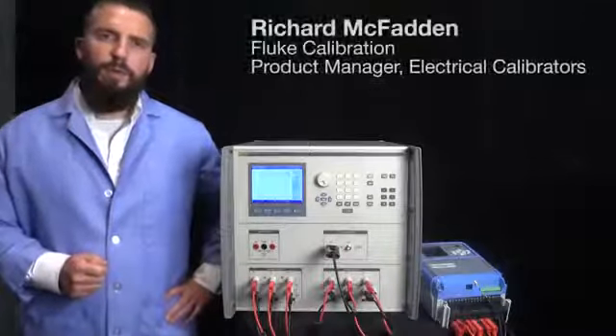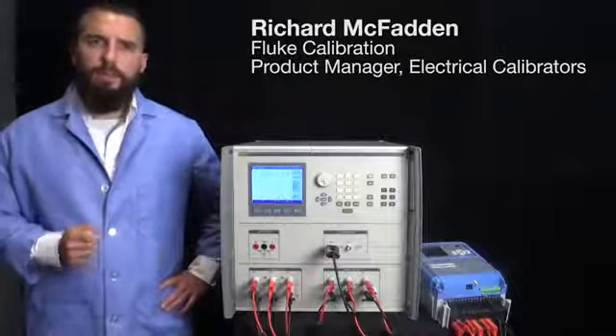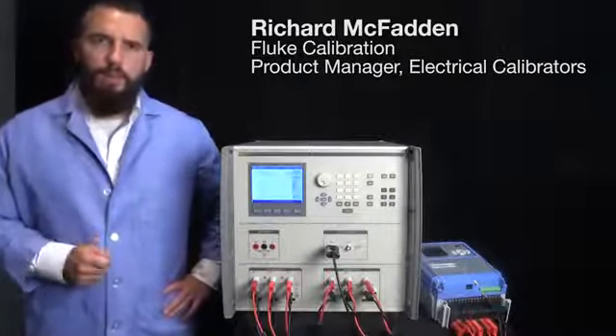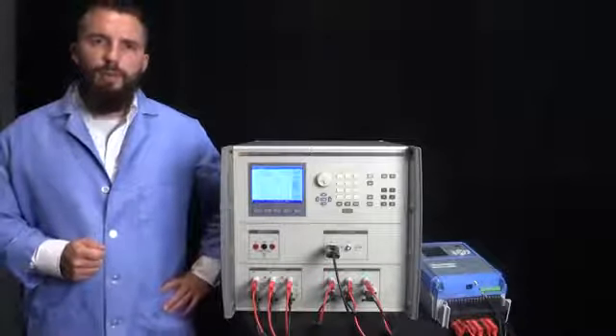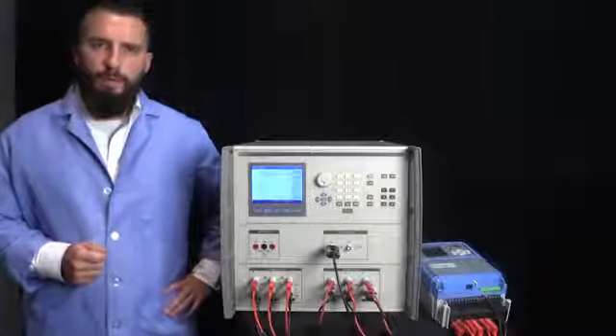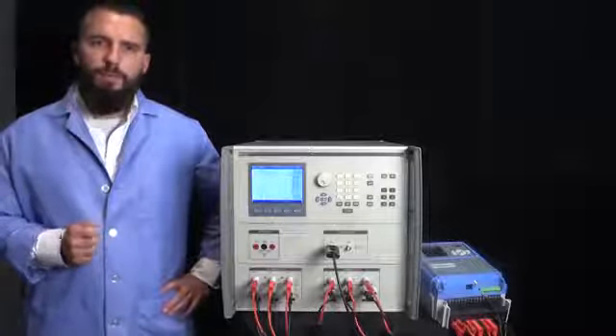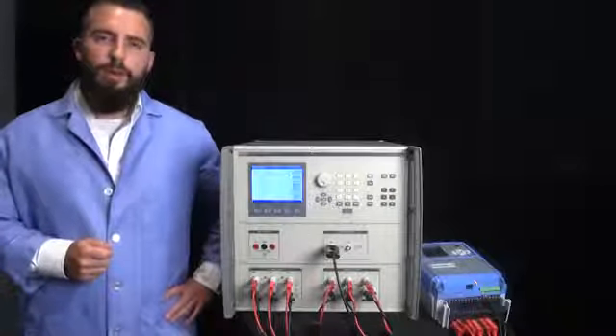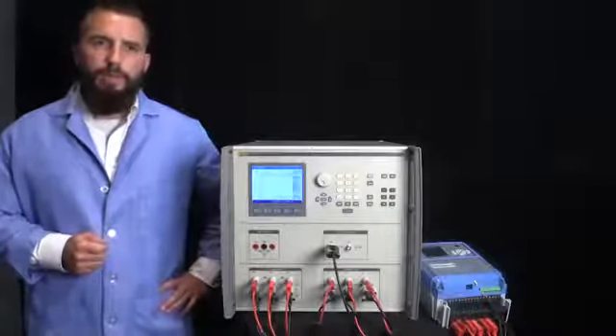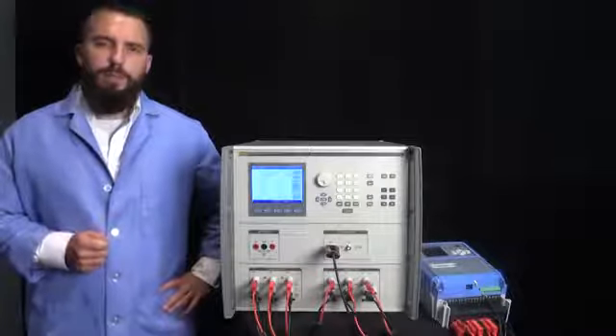Testing and calibrating three-phase energy meters can be difficult, time-consuming, and thus costly. This is mainly due to the process required to fully test and verify the output of the meter. Energy meters, almost without exception, use a technique of generating pulses to indicate the amount of energy they have measured. Each pulse represents a specific number of watt-hours.